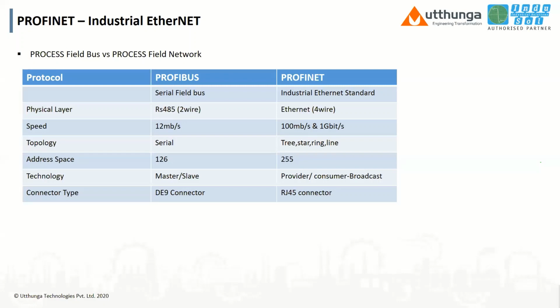So here we have designed some differences. What are the basic differences between Profibus and PROFINET? Profibus is a serial field bus, while PROFINET is an industrial Ethernet standard. Profibus is two-wire communication that we mentioned earlier. It is half duplex, while PROFINET is an Ethernet standard, like four-wire communication. It is full duplex, like I can talk and listen at the same time. That is why we are getting 100 Mbps speed and even 1 gigabit speed, while Profibus can only go up to 12 Mbps speed, and it is a serial communication.